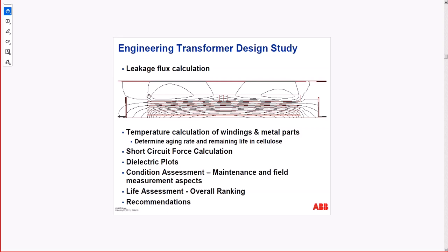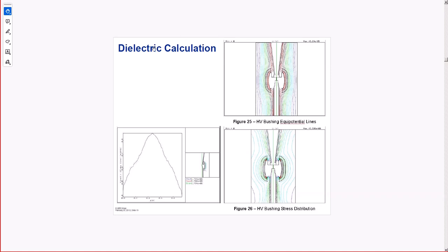One thing you should know, we also test the dielectric insulation between the magnetic core of the transformer and the tank, and that needs to be in the order of a minimum of 10 megaohms. So that's one of the tests that tells you that you are too close, or that something happened with the dielectric, with the oil inside the tank. So we should have at least 10 megaohms. Depending on the aging, it may be even higher for a new transformer, 100 megohms. Okay, so that's dielectric calculations.